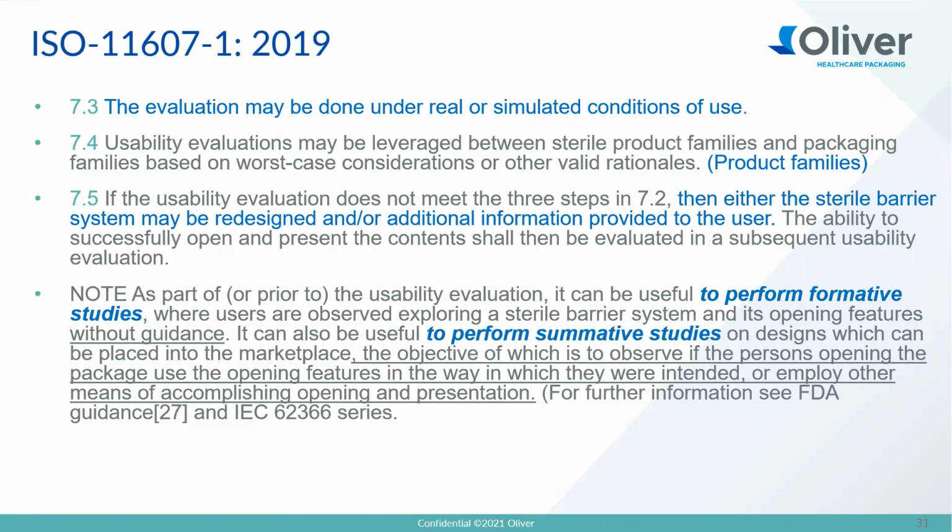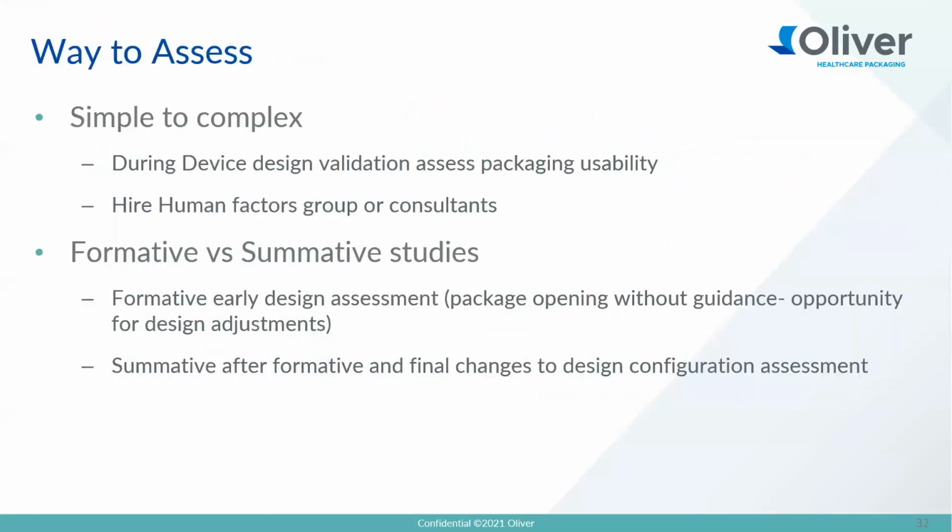And additionally, in the note, it talks about formative and summative studies. So, keeping ISO 11607 in mind, you can do this in many ways, and it's pretty loose, so you can either do this very simply or you can make it complex.